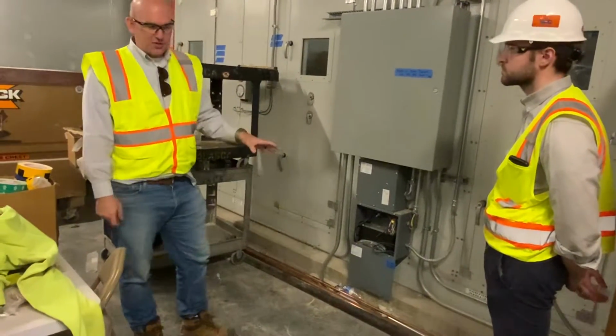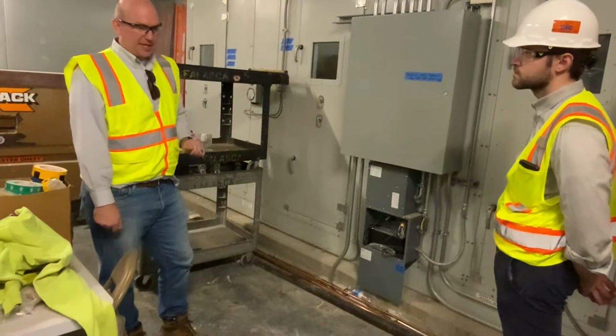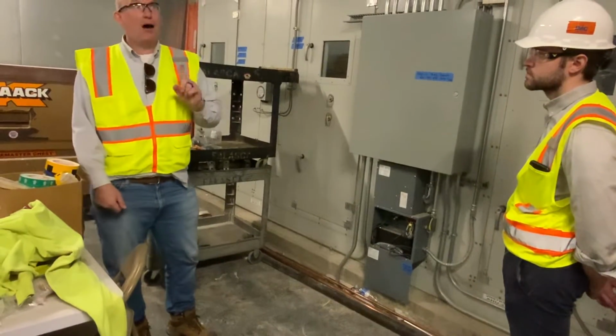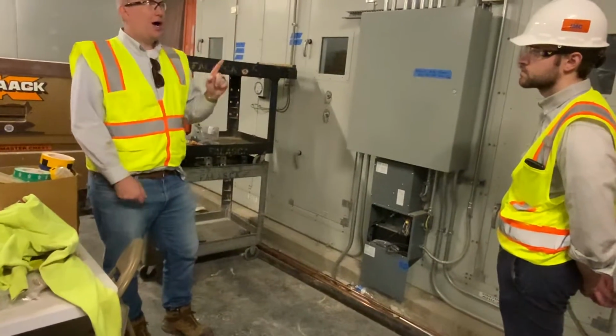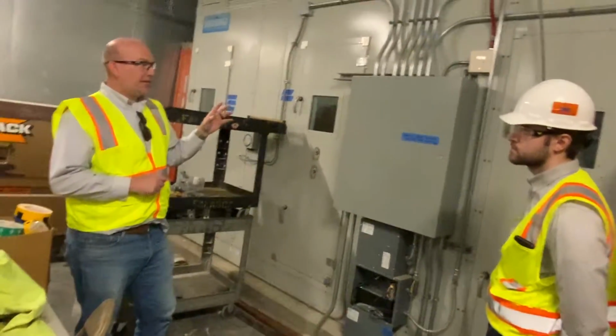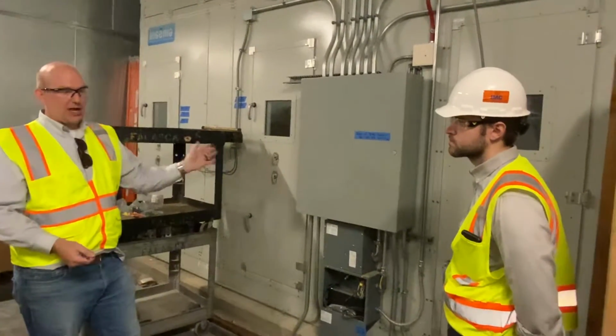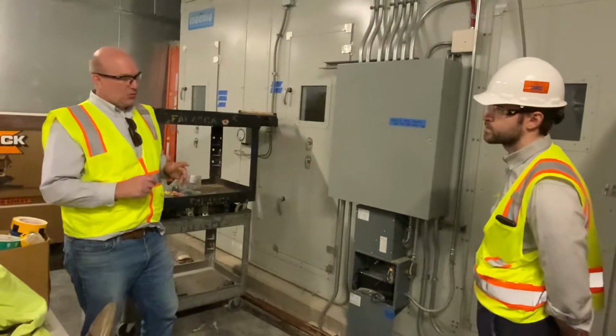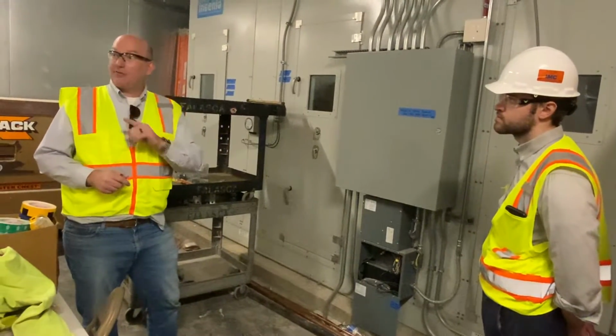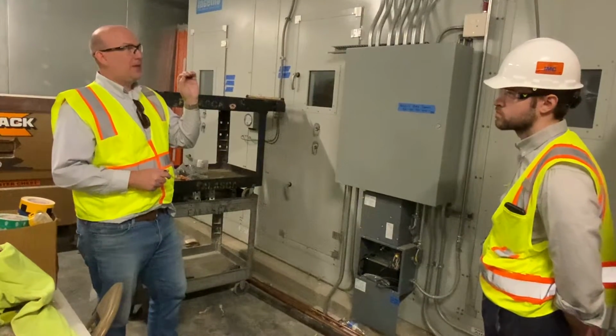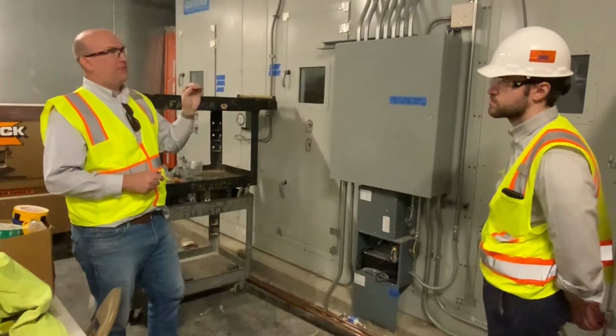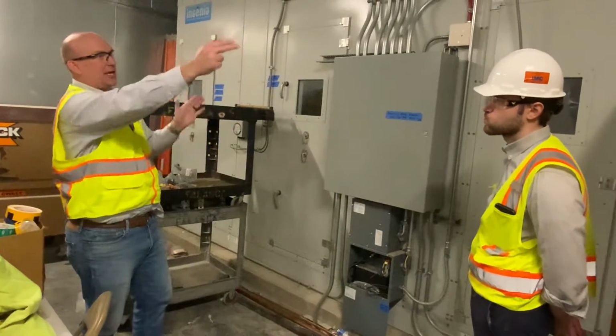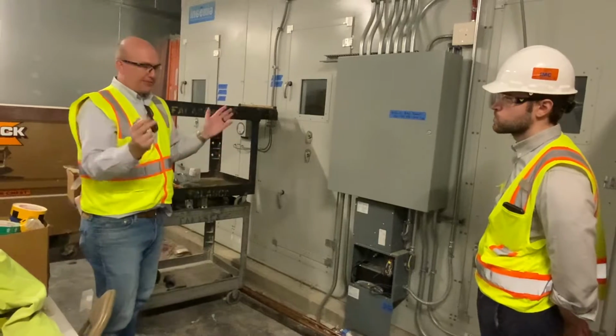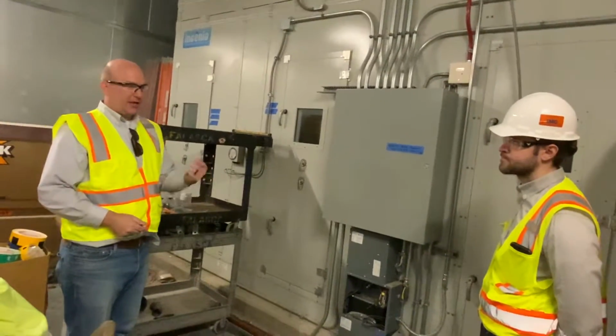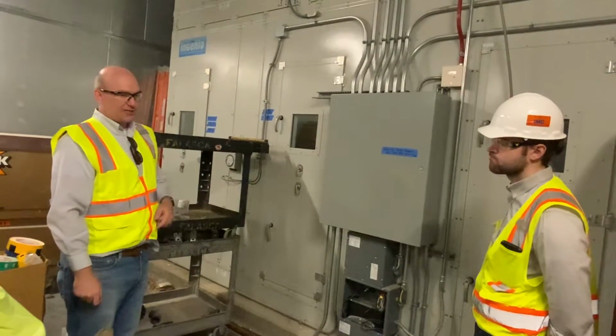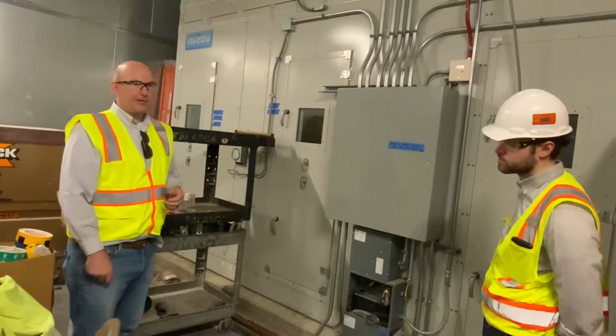The only thing that happens under emergency power for these air handlers, everything shuts down, except for one thing, which is modulation of the hot water valve to the hot water flow. A lot of air handlers would simply use a shutdown to fail the valve wide open, and if there's hot water, run hot water through the coil to protect it, right? We're not doing that here. We're actually still under a safety condition. Even a freeze-stat trip, we're still doing active control of the valve, meaning there are temperature sensors inside that we use for discharge, and if the air handler shuts down, that valve then controls just like the plenum, just like a room, to that temperature sensor, and keeps it at 70 degrees. So it keeps it from freezing.